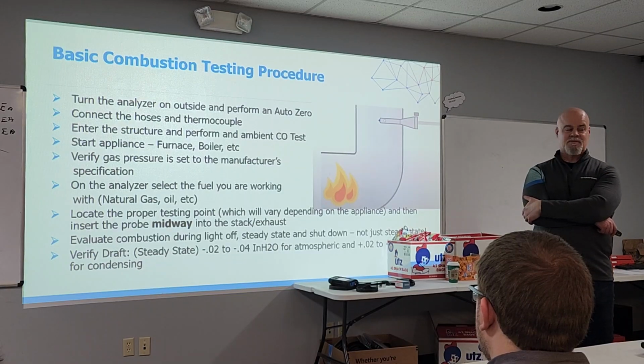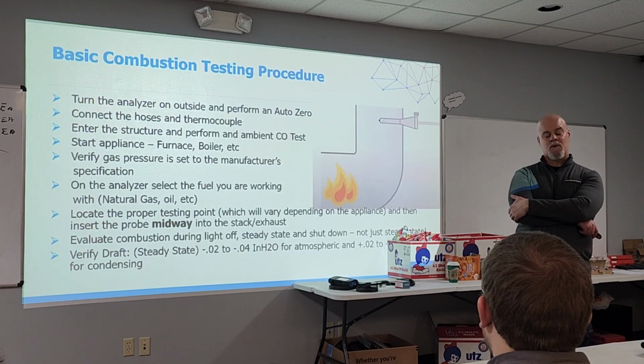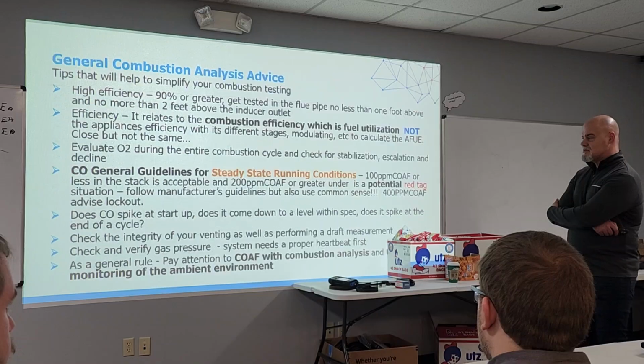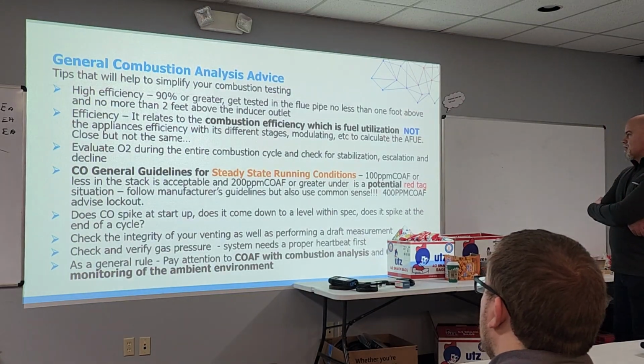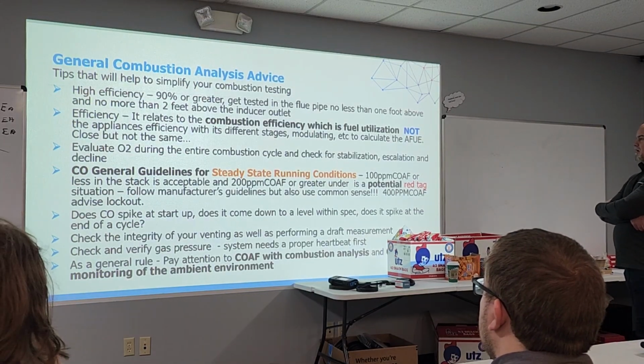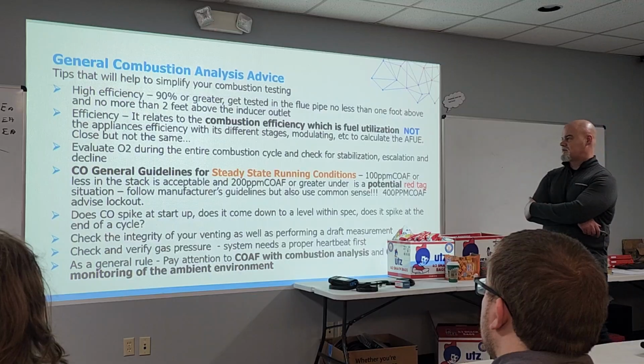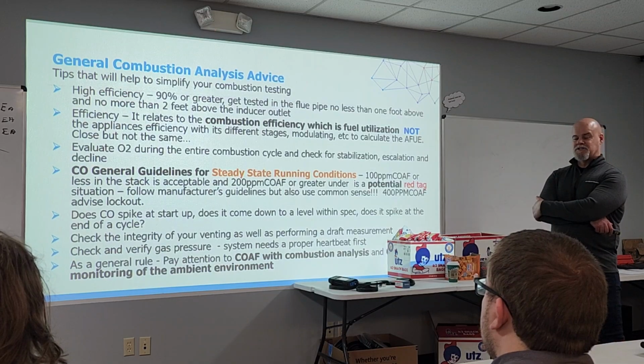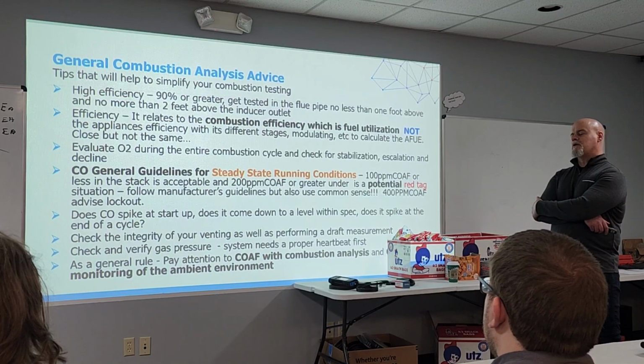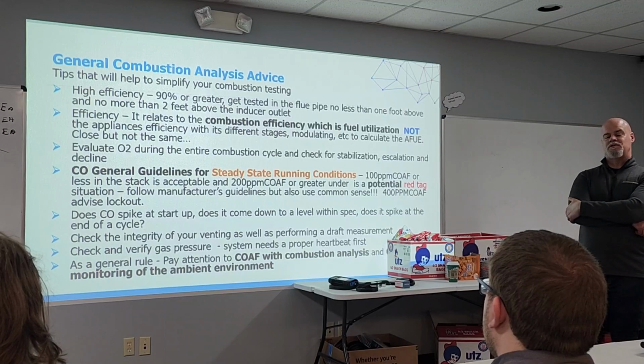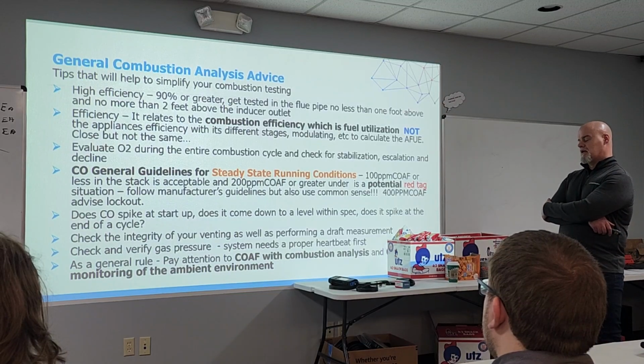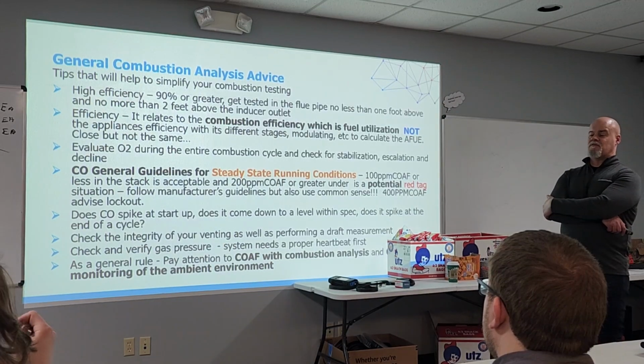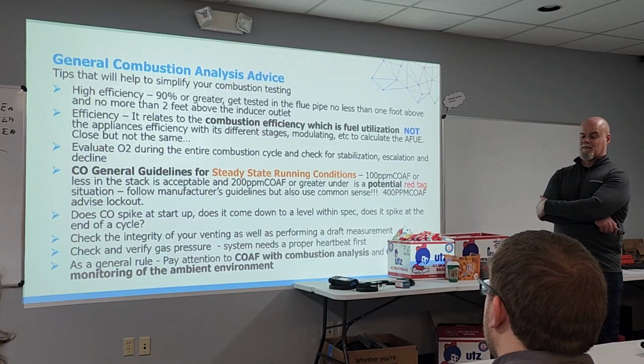For a condensing system or something with induced draft, it is positive 0.02 to positive 0.08. So, some combustion pearls from yours truly. I don't know if they're pearls, but they're little tidbits of information here. High efficiency systems, 90% or greater, get tested no less than 1 foot above the inducer outlet, but no greater than 2. Efficiency means fuel utilization on your analyzer.